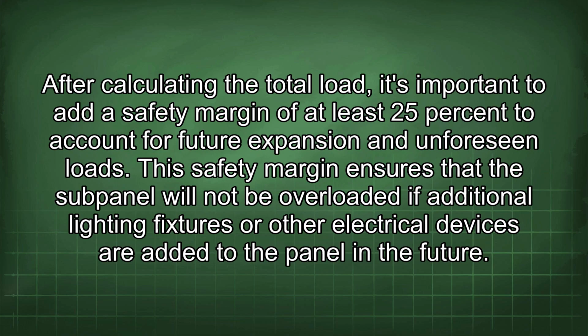After calculating the total load, it's important to add a safety margin of at least 25% to account for future expansion and unforeseen loads. This safety margin ensures that the subpanel will not be overloaded if additional lighting fixtures or other electrical devices are added to the panel in the future.